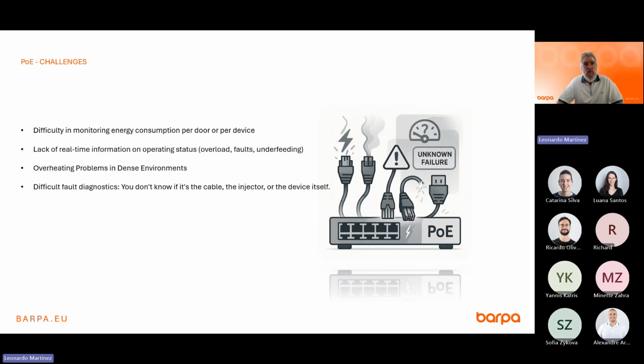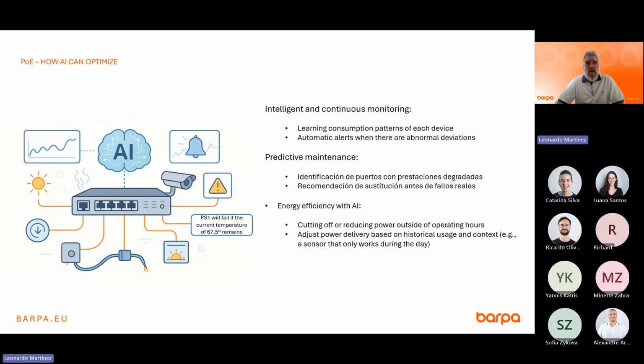So as we ask for more and more power, these PoE devices get stressed. Lack of real-time information and operating status will be really a trouble. That makes fault diagnostics very complex, and you don't know when a fault occurs if it's the injector, the PoE switch, the powered device itself, or the cable.